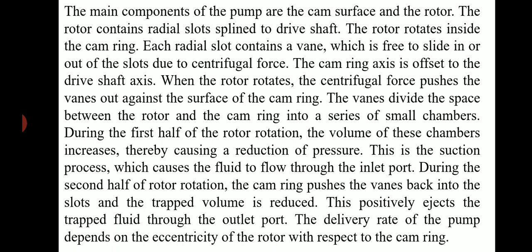During the second half of rotor rotation, the cam ring pushes the vanes back into the slots and the trapped volume is reduced. This positively ejects the trapped fluid through the outlet port. The delivery rate of the pump depends on the eccentricity of the rotor with respect to the cam ring.